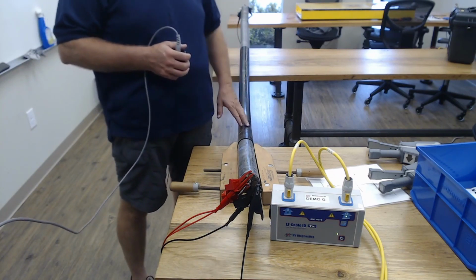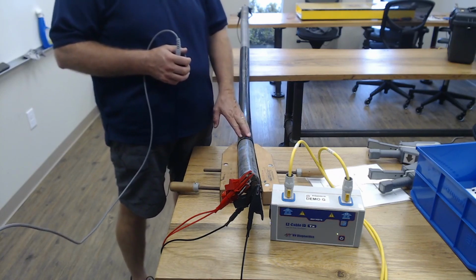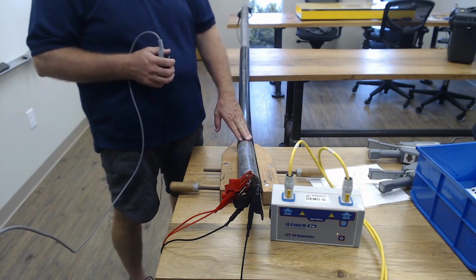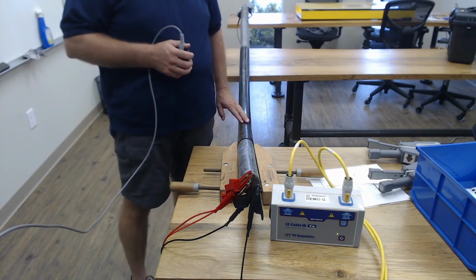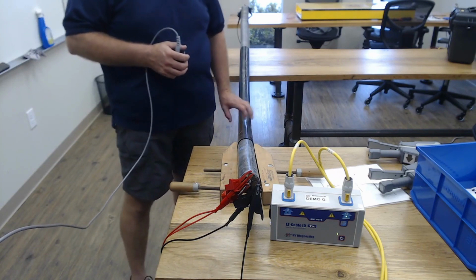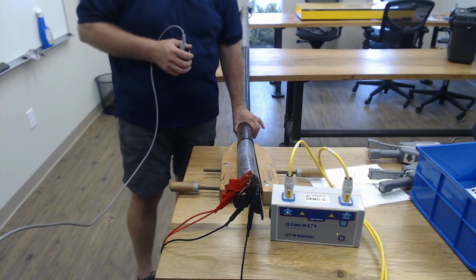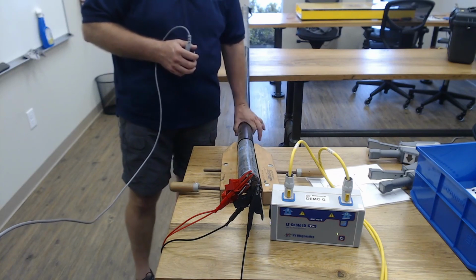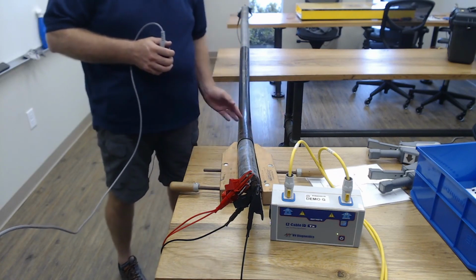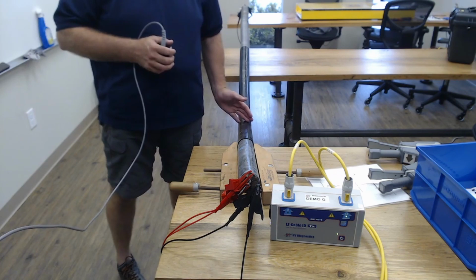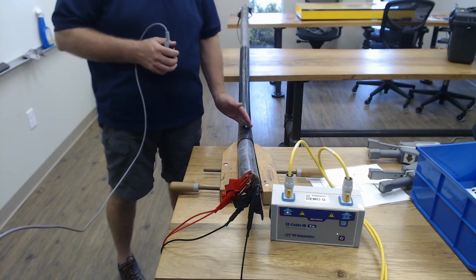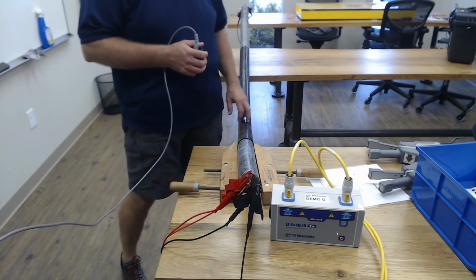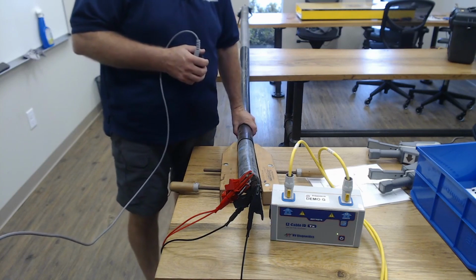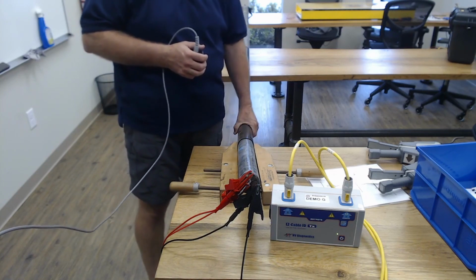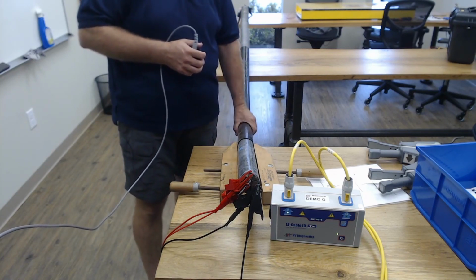Only the cable in question. So not only are you identifying the cable in question, but you're actually identifying the phasing under the cable. So one of our utilities, they will actually mark on the outside of the jacket A phase, B phase, and C phase. So when they cut, they already know what the phasing is underneath the cable. So they can make sure that whatever they join to it, the A goes to the A, the B to B, and the C to C, etc. So it's a very powerful tool of not only identification, but also of phase identification as well.